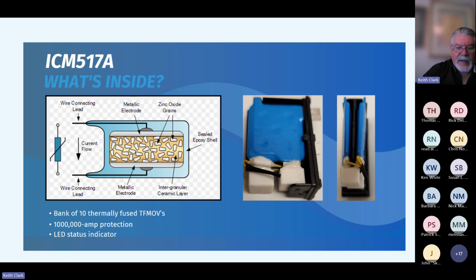There's a bank of 10 in this device, and each one of these TMOVs operates independently and will take that hit. And if it's able to, without completely degrading the TMOV, it will take those hits and dissipate that heat off. It's filled with zinc metal oxide grains, like I say, which have real good heat dissipation properties, and will dissipate that heat away.